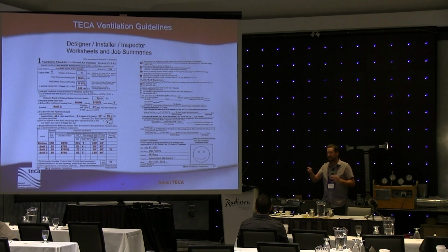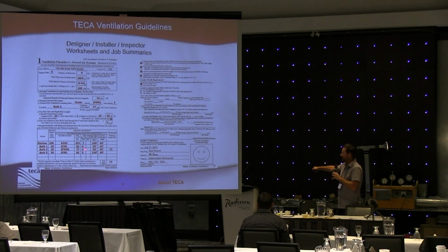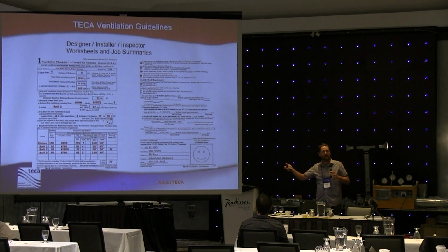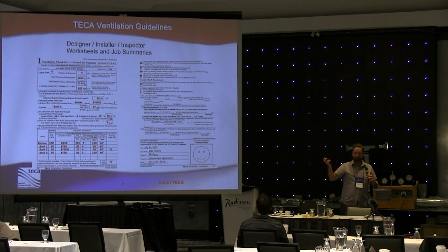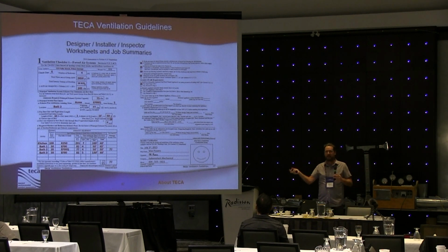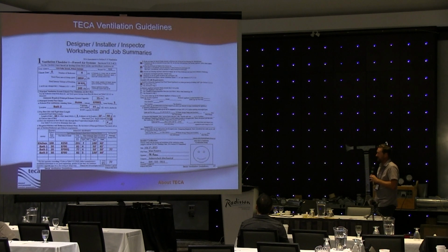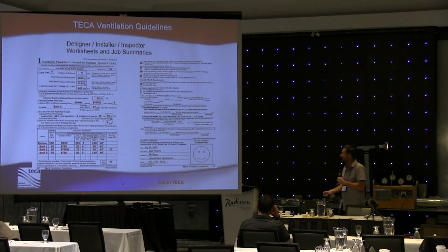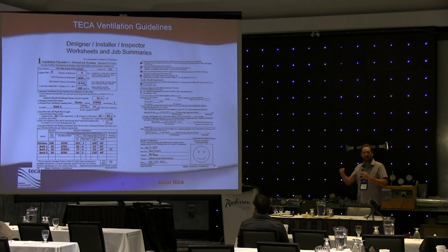But you're going to come in as the AHJ, and you're going to look at this and say, well, this is all existing stuff. There's nothing we can do to change it anyways, right? If it's from the early 80s through the 90s, the ductwork is probably all undersized anyways, and before that even. It's probably undersized, especially on the exhaust fans, if they even exhaust to the outside. Some of them even just dump into attics. So really, where do you draw that line?